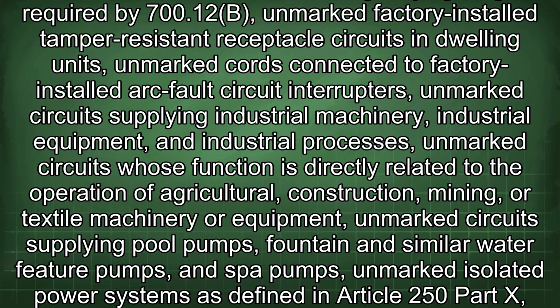There are exceptions for marked factory-installed branch circuits for emergency lighting as required by 700.12(B), unmarked factory-installed tamper-resistant receptacle circuits in dwelling units, unmarked cords connected to factory-installed arc fault circuit interrupters, unmarked circuits supplying industrial machinery, industrial equipment and industrial processes, unmarked circuits whose function is directly related to the operation of agricultural, construction, mining, or textile machinery or equipment, unmarked circuits supplying pool pumps, fountain and similar water feature pumps and spa pumps, unmarked isolated power systems as defined in Article 250 Part X, and replacement of arc fault circuit interrupters is permitted without replacement of the marking.